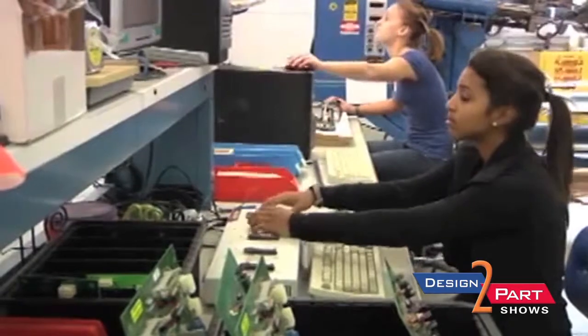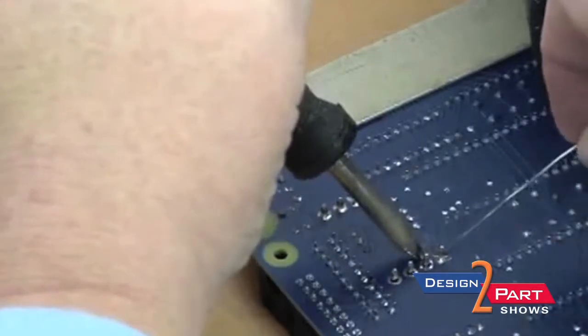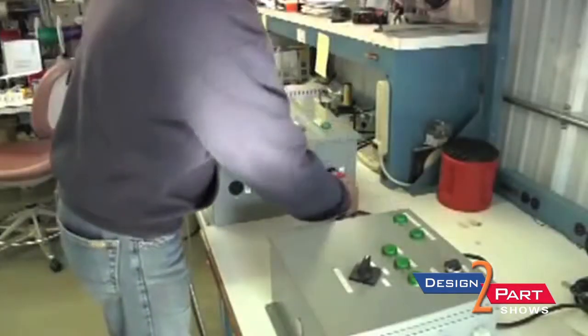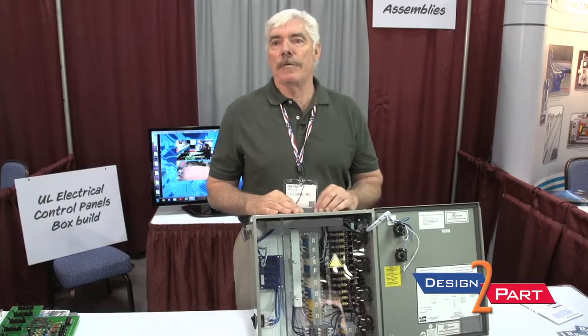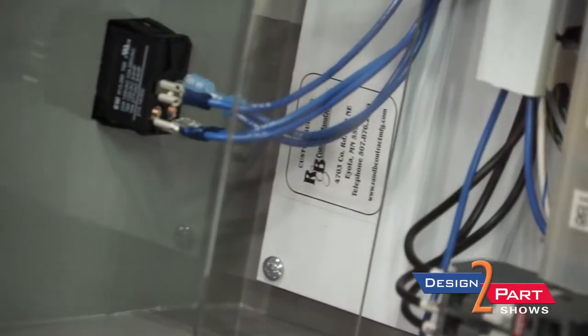Once the enclosure's finished, we'll power them up. We have available within our facility 110, 230, and 230-volt three-phase power, so we can put power to the controls. We can check out PLCs, relays, those kinds of things, and make sure that everything functions correctly. We also go through a visual inspection where we double-check tightness of all the connectors and relays, and make sure that everything's mounted correctly and correctly labeled.